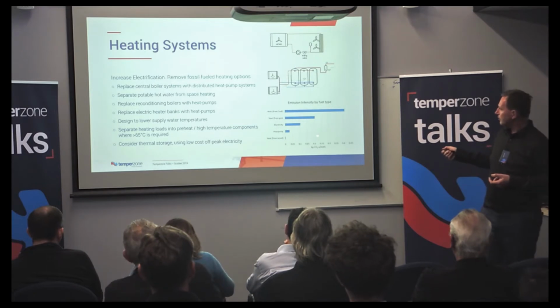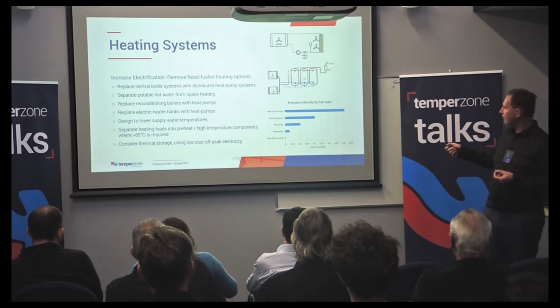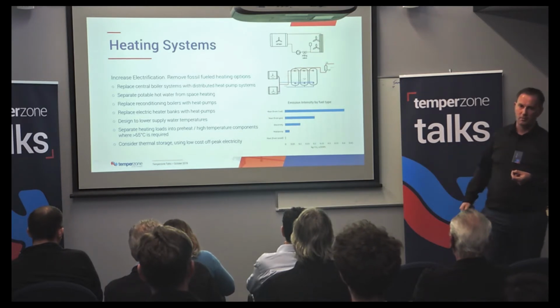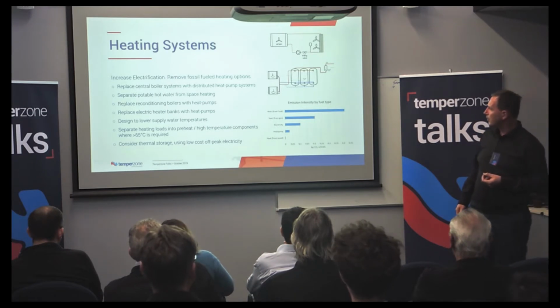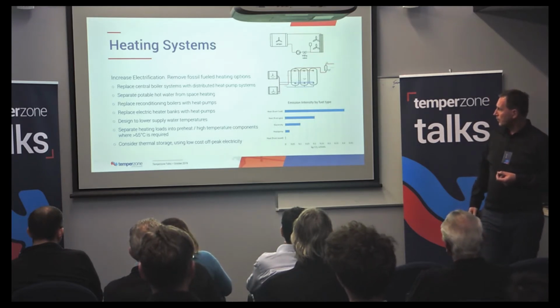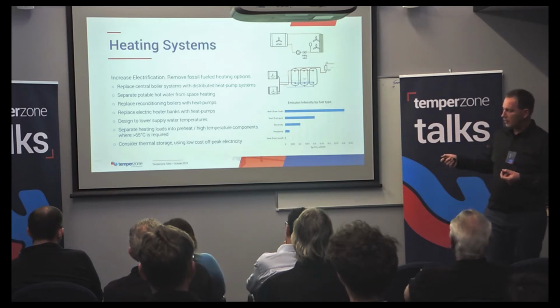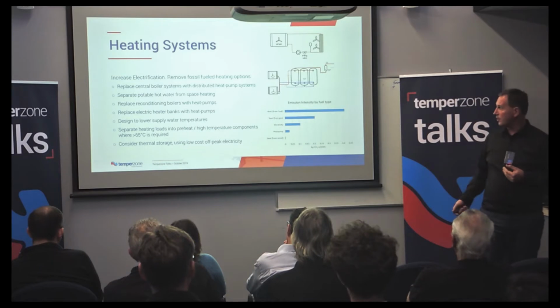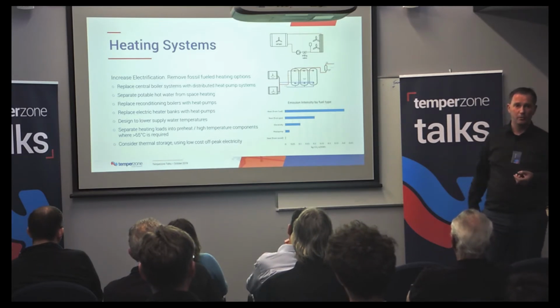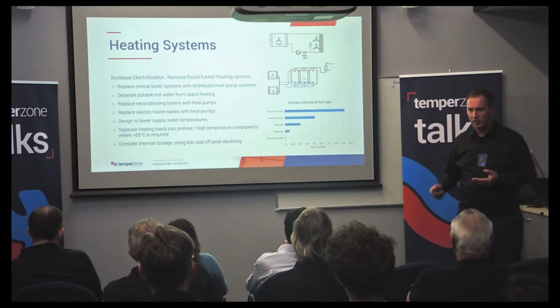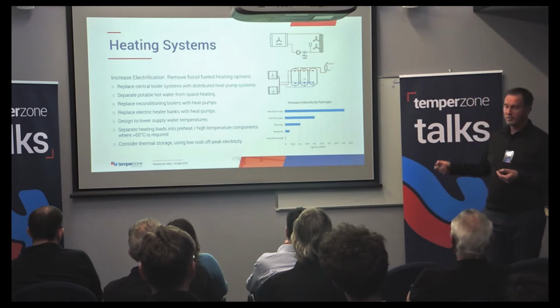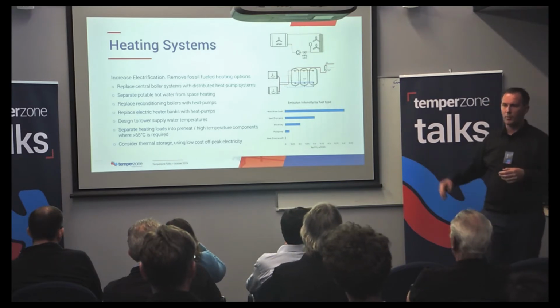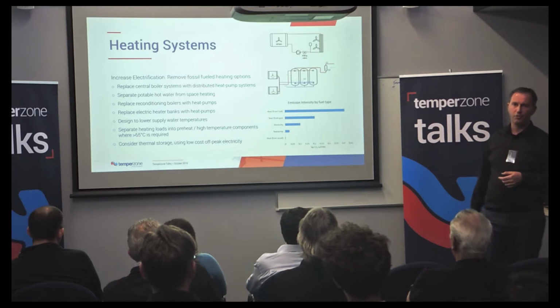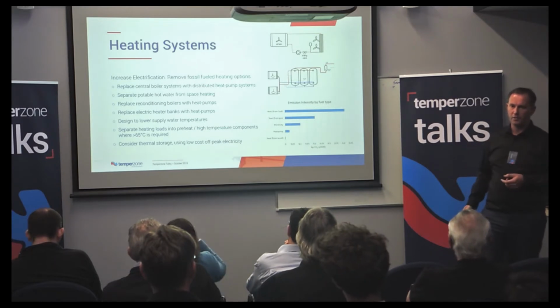If you look at the emission intensity on different fuels, you can see electricity, we can reduce that greatly using heat pump technology. And if you're doing new space heating designs, designed to a little bit lower temperature, there's a huge difference between design to 60-65 versus design for 55. You go from a COP of 1.2, 1.3 to a COP of over 3 with a small 5-degree change.